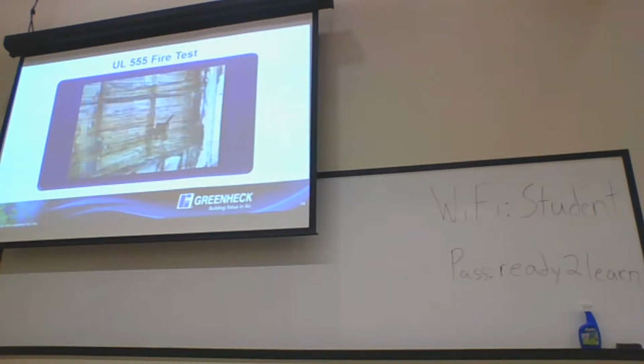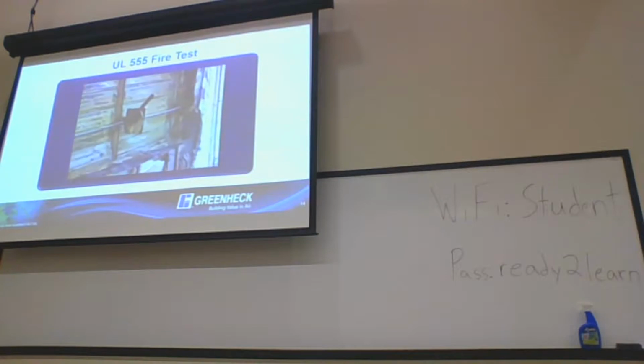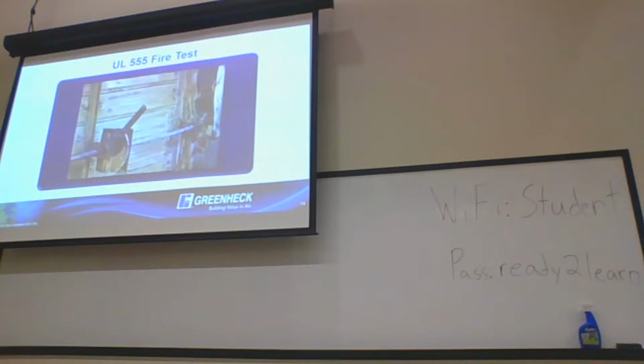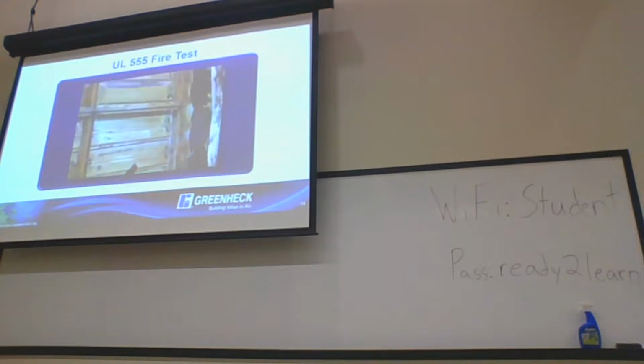So he's giving an initial assessment, making sure there are no 1/8 inch through holes. And like I said, they go through the damper on the assessment side of things and really poke and prod through it. So that gives you an idea. And after the UL fire smoke tests, I think on our size furnace, it's about $6,000 of gas to run that furnace for that UL test. So it gives you an idea of how many BTUs the thing is putting out.